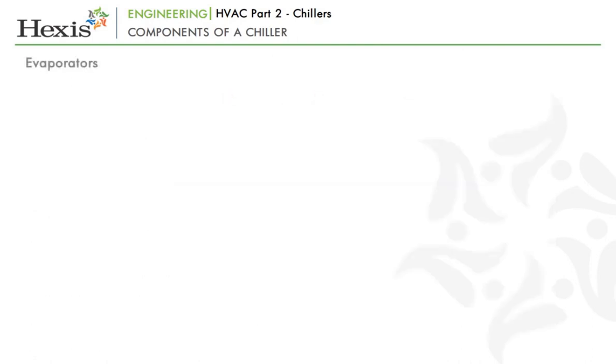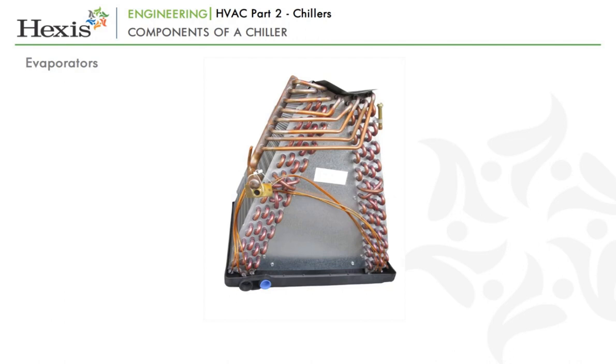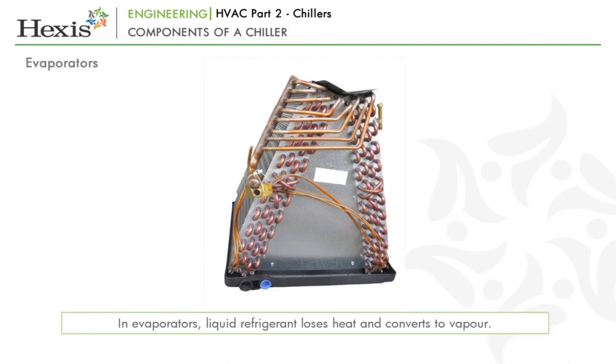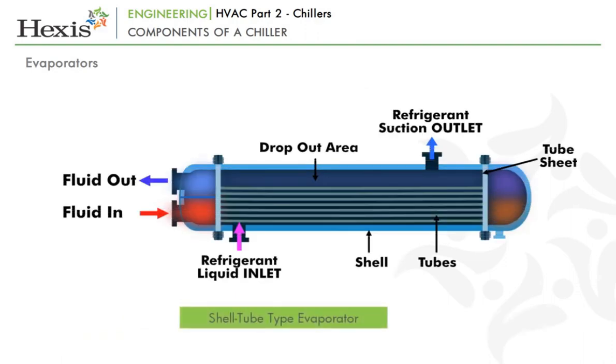The last component of chillers that we are going to discuss is the evaporator. As learned in the previous module, evaporators are where the liquid refrigerant loses its heat and converts to vapour, thereby cooling the medium. In a chiller, the evaporator is of the shell and tube type, just like the one seen in the condenser. The refrigerant could be in tubes, i.e. dry expansion, or in the shell, i.e. flooded type, while the water will be on the other side.